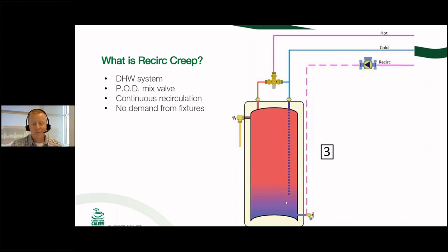And what you're actually going to have the ability to do by traveling backwards up this dip tube is, again, through the stratification of the tank, you're actually going to be adding more heat to that recirc. So you're going to need even less heat to bring that loop up to temperature to make sure you're maintaining that 120 degrees. Okay, so it's something that I would say with a mixing valve application, if you're piping it like this, I would try to avoid it.